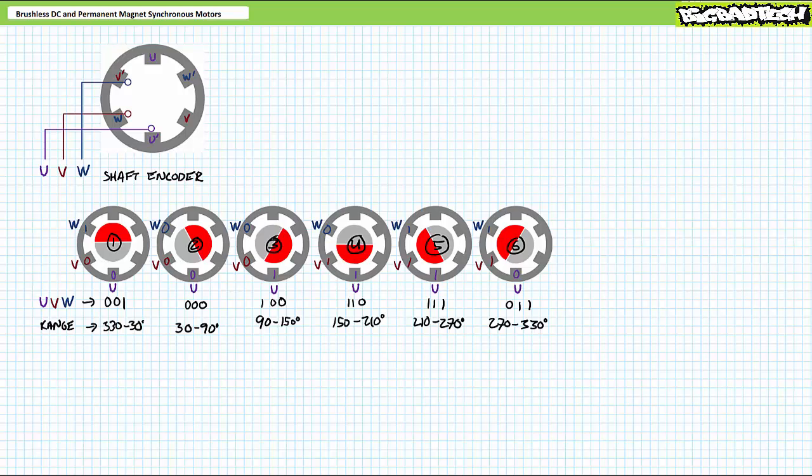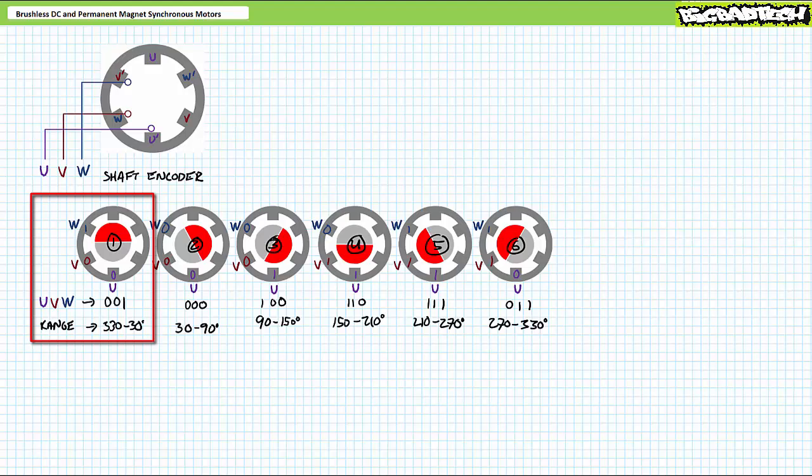More sophisticated higher-resolution implementations would divide the rotor into smaller angular segments. With the rotor pointed straight up and down, U registers zero, V registers zero, and W registers one, making this position from 330 degrees to 30 degrees UVW-001. For those with a background in digital systems, you'll note it is simply by sheer coincidence that binary number 001 happens to equal the decimal number one. This is not true for the remaining steps.